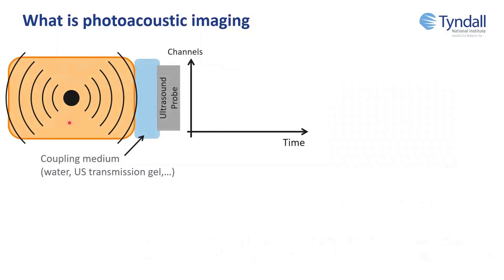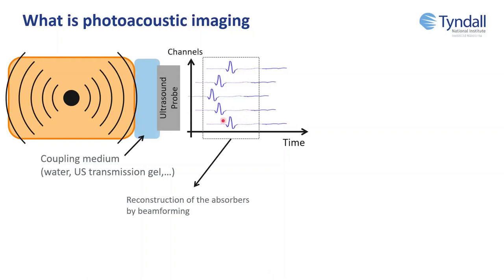If you can detect that wave, you can recover information about the object that actually absorbed the light. How it's usually done: you have your piece of tissue with an absorber that emits ultrasound waves, then you have a coupling medium and place an ultrasound probe. Depending on the channel on your probe, you detect pulses at different times. Using a technique called a beamforming algorithm — which does time-of-flight analysis — if you know the speed of sound, you know how long it took to travel and can reconstruct where the absorber was. This technique has been developed widely over the past 20 years, and now there are some incredible images.